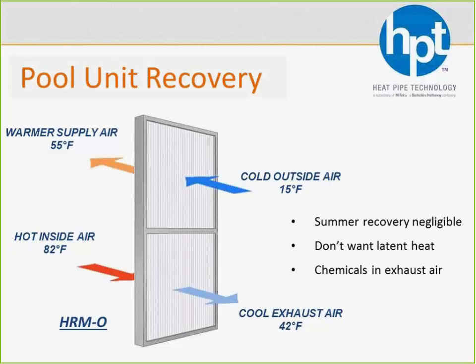It's also beneficial that we are a sensible only device. When it comes to pool areas, you actually want to get rid of that humidity instead of bringing that latent heat back in. So the fact that we're only recovering sensible heat is a good thing when it comes to pool units. And it's also good that we don't have cross-contamination, because any of those chemicals, you don't want to bring them back in. We're going to exhaust all of them right out of the room. So if you have any pool units or applications, the heat pipe's going to allow you to shrink that system down, save some energy, and it kind of fits right in line with what pool units want to do.